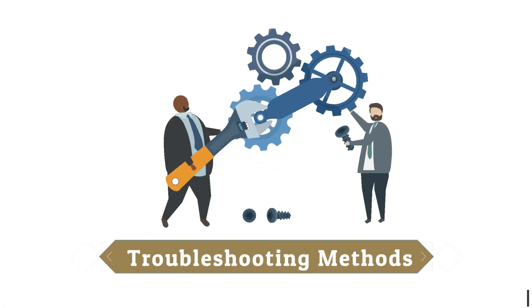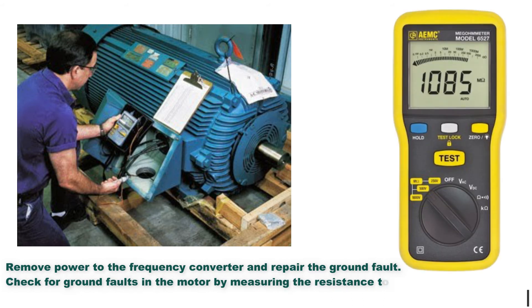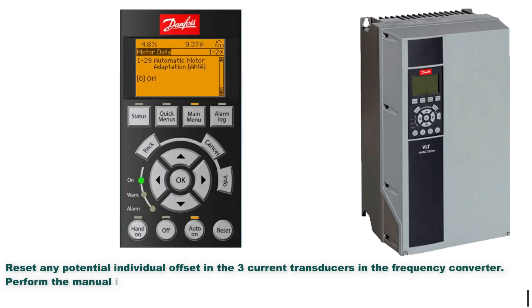Troubleshooting methods: Remove power to the frequency converter and repair the ground fault. Check for ground faults in the motor by measuring the resistance to ground of the motor cables and motor with a megohmmeter. Reset any potential individual offset in the three current transducers. Perform the manual initialization or perform a complete AMA — this method is most relevant after changing the power card.